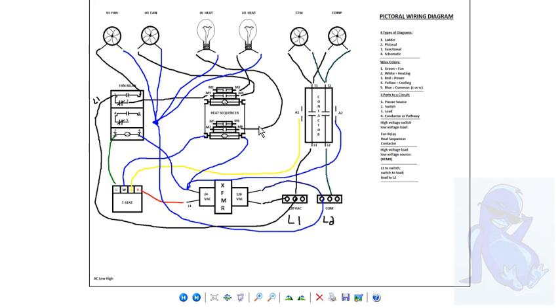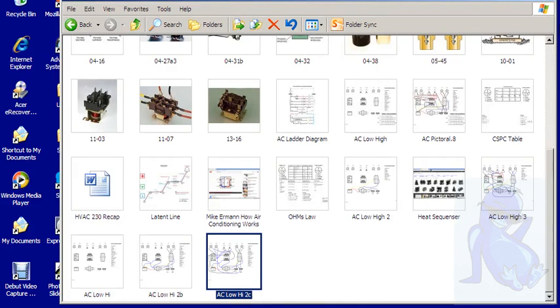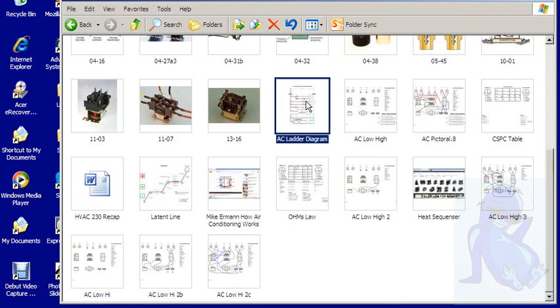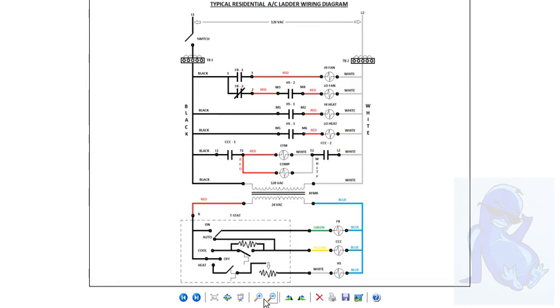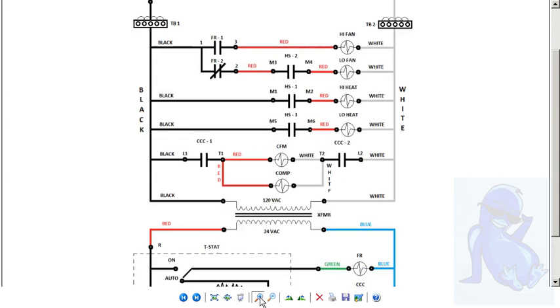So that's what we wired up. That is the low and the high circuit, 24 volts and the 120, and actually your condensing unit's probably going to be a higher voltage, 220, but we won't worry about that right now. So if you understand this, you can wire up the system. And that leads us to ladder diagrams. Here's a ladder. Zoom into that ladder.